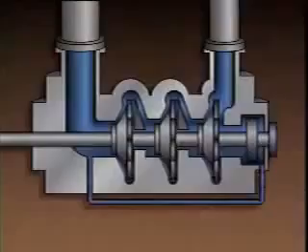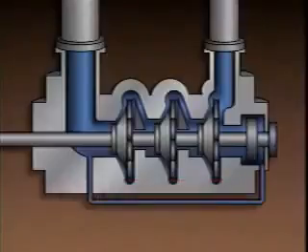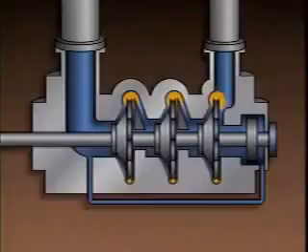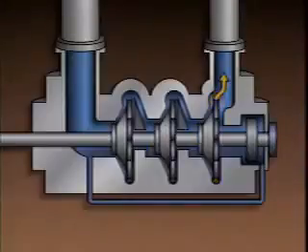All centrifugal pumps work by creating a centrifugal force that moves the liquid and increases its pressure. In applications where large increases in pressure are needed, multi-stage centrifugal pumps are often used. A multi-stage centrifugal pump contains two or more impellers and volutes in a single casing. In a three-stage pump, each stage has its own impeller and volute. The liquid's pressure increases in each volute, and each of the first two volutes discharges into the suction eye of the next stage. The third stage volute discharges into the pump's outlet.